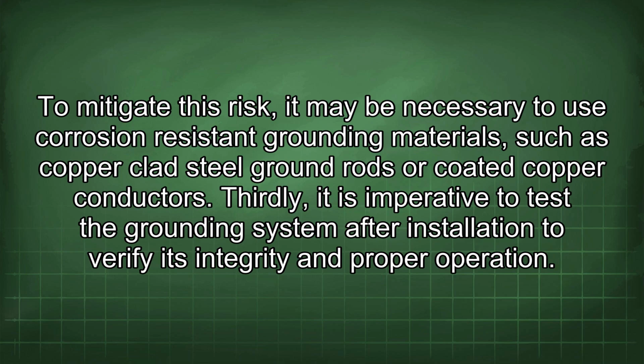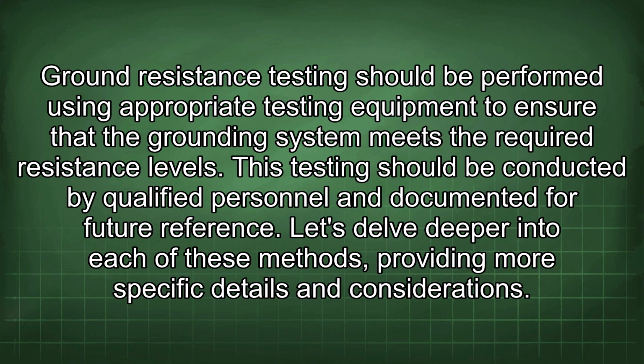coated copper conductors. Thirdly, it is imperative to test the grounding system after installation to verify its integrity and proper operation. Ground resistance testing should be performed using appropriate testing equipment to ensure that the grounding system meets the required resistance levels. This testing should be conducted by qualified personnel and documented for future reference. Let's delve deeper into each of these methods, providing more specific details and considerations.